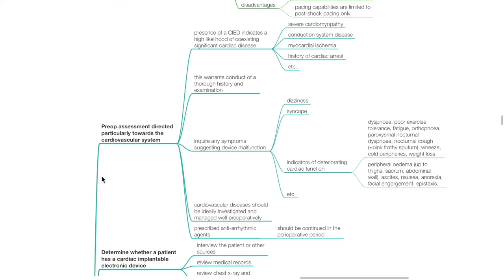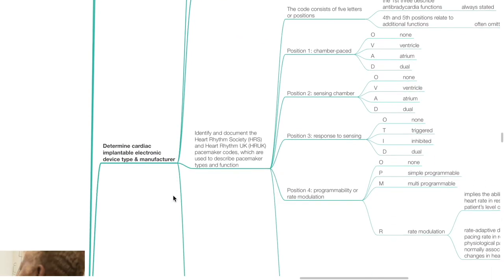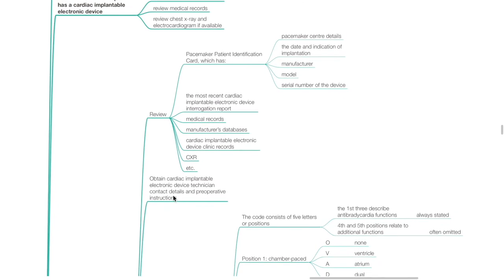Cardiovascular diseases should ideally be investigated and managed well preoperatively. Prescribed antiarrhythmic agents should be continued in the perioperative period. Determine whether a patient has a CIED by interviewing the patient or other sources, reviewing medical records, chest X-rays, and electrocardiograms. Determine the CIED type and manufacturer. Review the pacemaker patient identification card, which has pacemaker center details, the date and indication of implantation, manufacturer, model, and serial number. The most recent CIED interrogation report, medical records, manufacturer databases, and cardiac implantable electronic device clinic records can be reviewed.